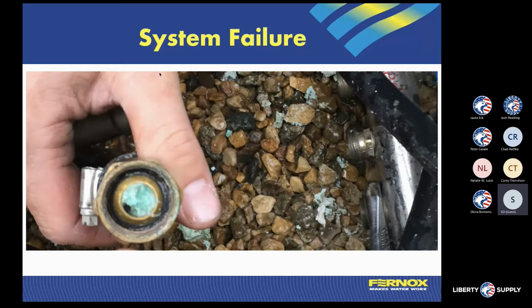So there's some visual inspection you can see in the mechanical room. So when you're walking through a mechanical room, if you see that aqua color on your copper pipe, that means there was a leak. Copper breaks down as a liquid and it'll dry to that similar aqua color. So you can see rust spots on steel, white calcium buildup, that's corrosion that has escaped out and then dried from that system standpoint. So we're going to be able to also have visual examples of why that water quality has started to come into the system.